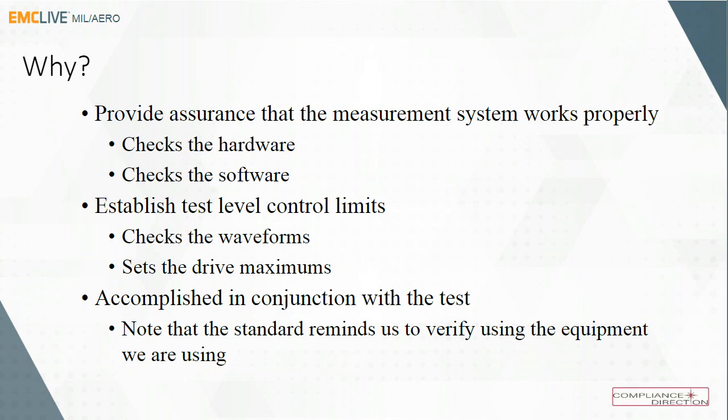And if everything is connected right, all of the various components in a typical configuration, we should get the right answer. And our software brings in correction and conversion factors and things of that nature. And the hardware has all kinds of connections made with potential for attenuators, filters, etc. And all these components get validated by having a known signal that we measure. There's also a second part to that, to establish some test level control limits.